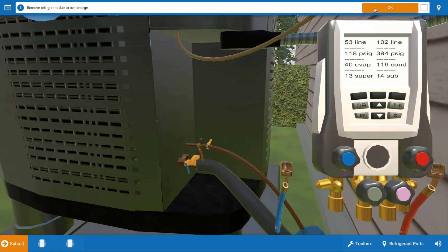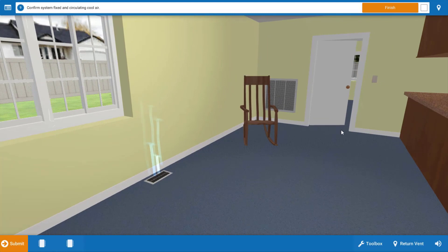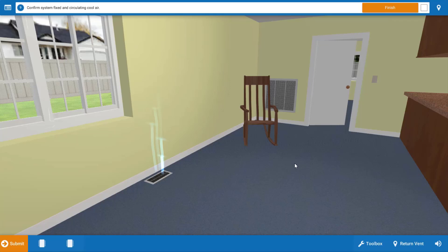We're going to click OK in the procedure guide and what I would tell you to do next is observe one full cycle of operation to make sure everything's working properly. I would also pull the indoor filter and clean it or replace it if necessary, just a little added value for the customer. Last but not least we're going to go to the residence and verify that cool air is being delivered through the floor register here and we can see from our graphic that in fact it is. So we've solved this problem.